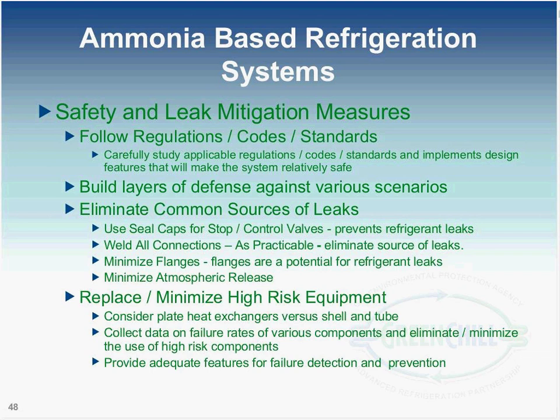But when you use ammonia, that reduces to multiples of 10. You're talking about 40 pounds, 50 pounds, 80 pounds. So there's significant potential for reduction of the charge. You have completely natural refrigerants. You have the potential for minimizing the leaks, and this is guaranteed to give you platinum level certification.